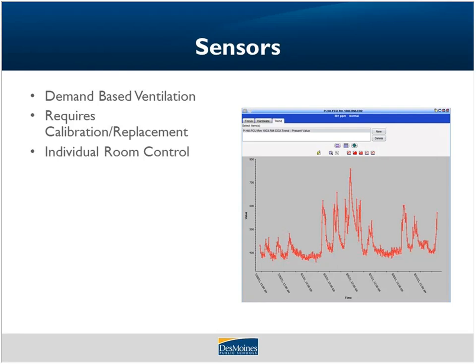The thing with sensors is they require calibration and replacement. A bad sensor doesn't provide good information and can't accurately tell the damper where it should be. It becomes a very important PM, preventive maintenance, task for our staff to maintain all these sensors.